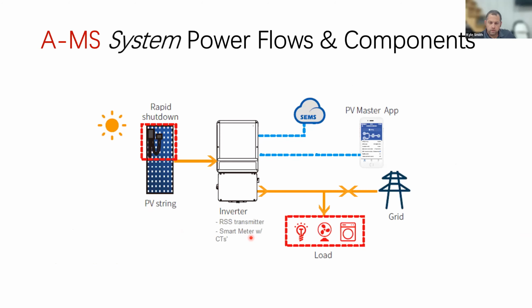Great, got it. So a PV system is very basic compared to a hybrid. We understand that there's just power flow from the PV into the inverter and back out on the AC side, whether to feed loads or extra power going to the grid. And of course, grid power can come in, feed the loads, and be sensed by the inverter. Because this is a PV inverter, it has to sense the grid, right? It has to shut down if the grid goes down. So it's an on-grid inverter. The dotted blue lines indicate these virtual connections, right? We have connections through our Wi-Fi dongle, for example, to our SEMS system.